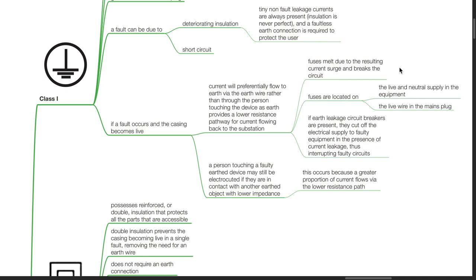Earth provides a lower resistance pathway for current flowing back to the substation. Fuses melt due to the resulting current surge and break the circuit. If earth leakage circuit breakers are present, they will cut off electrical supply in the presence of current leakage. A person touching a faulty earthed device may still be electrocuted if they contact another earth object with lower impedance, as greater current flows via the lower resistance path.